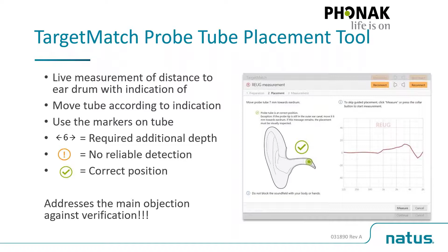Then after we have placed the probe tube, we move on to obtain the acoustic transformation measurements. What are those? Those are the RECD, the real ear coupler difference, and the microphone location effect. Through this process, it's going to use the hearing aid as a high impedance transducer to obtain the on-ear RECD. The microphone location effect is completed via microphone check simultaneously on both ears.